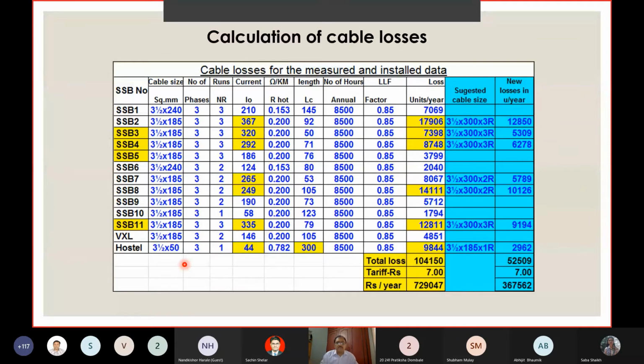Now, if you read about cable selection, spend a little time to understand this. You will have to make cable selections for short circuit current, and for reducing the voltage drop depending on the length and the cross section, so that you understand what is the voltage that has to be applied at the end use loads, the motor terminal. As you can see here, we have done this calculation by using the number of phases, that is 3 phase, number of runs, 3 runs, current carrying capacity, current measured by us during the audit, and the resistance from the cable catalogs.